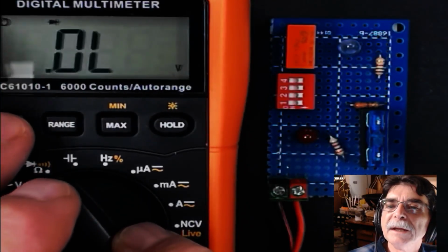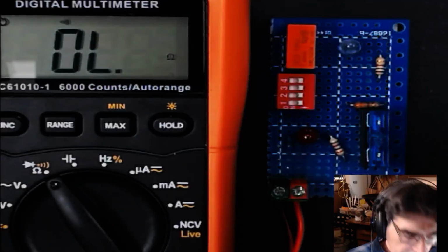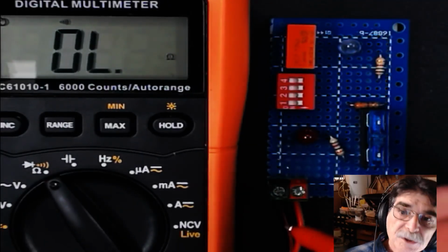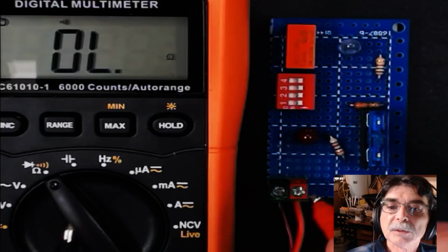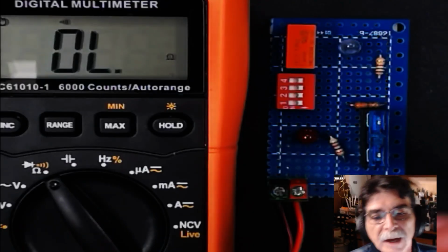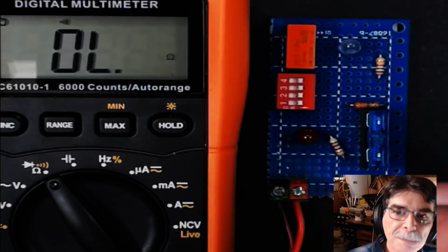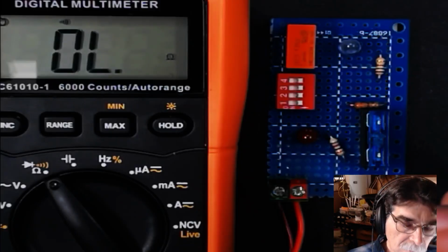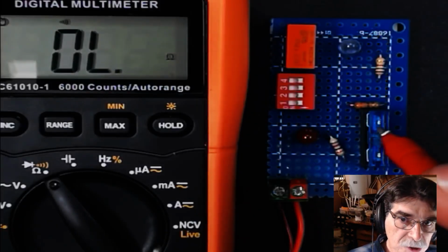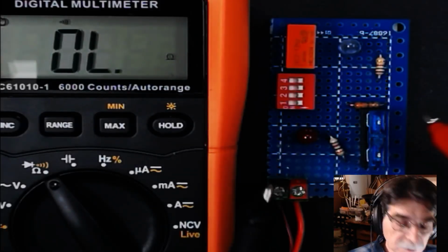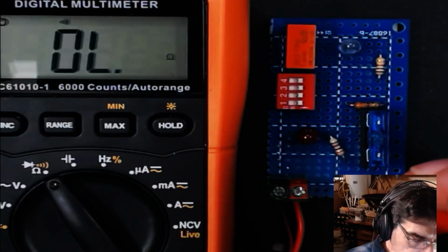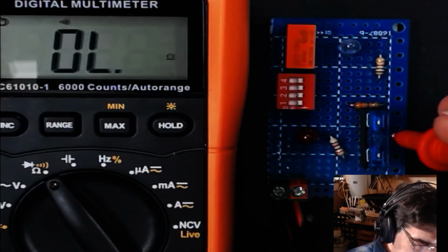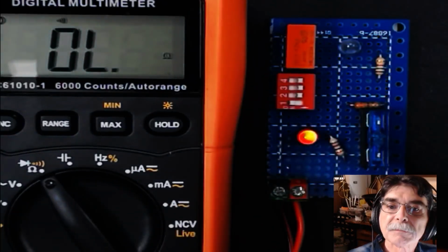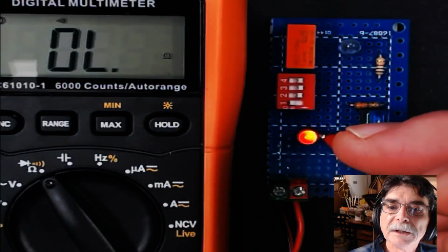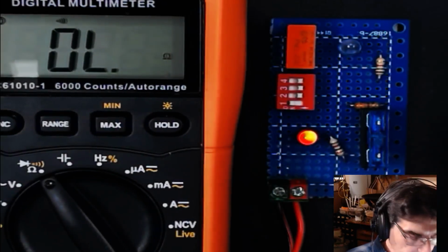So now I'm going to show you why you do not use continuity to check a fuse in a live circuit. If the circuit was completely de-energized, in other words, you shut your main battery switch off and you have no power to the battery, then by all means you can check continuity because there's no power in the circuit. But in our case, we do have power. And we know that because we've got our LED on telling us that we have a blown fuse.